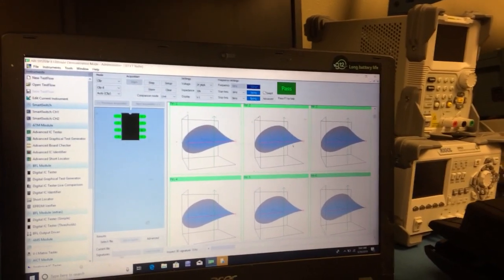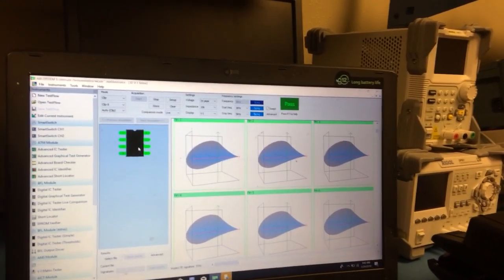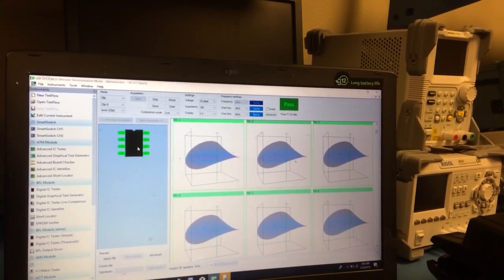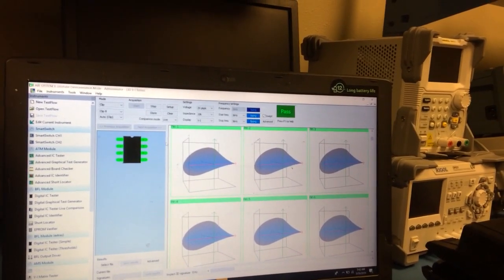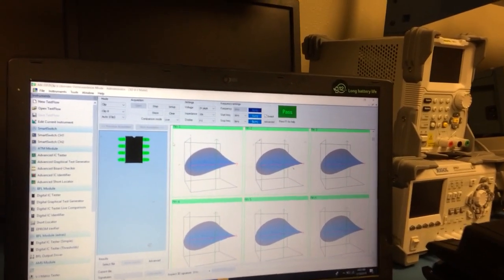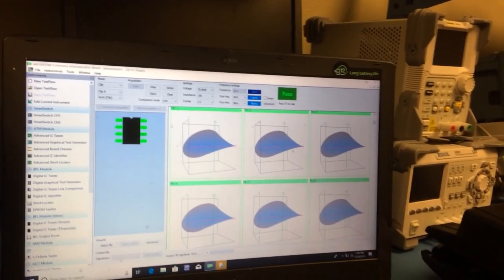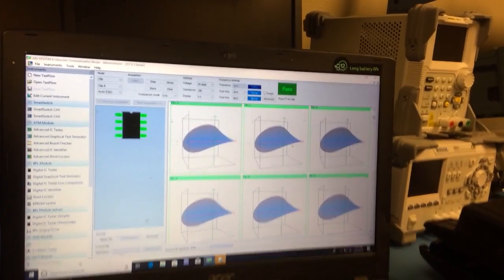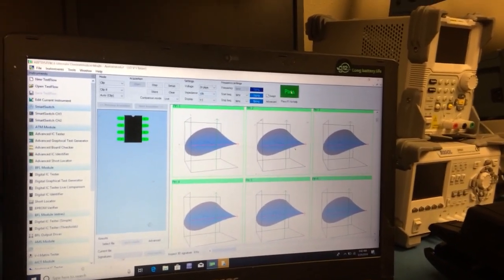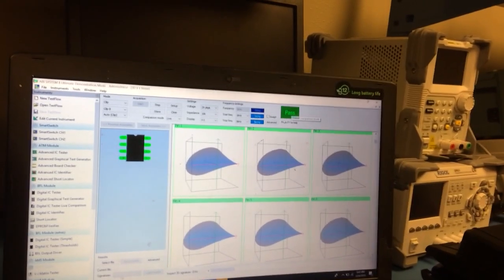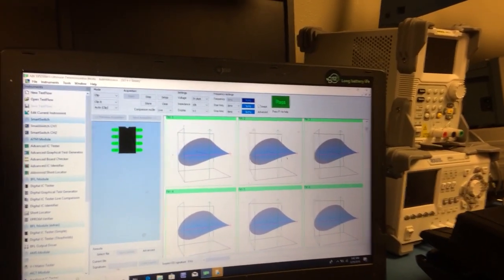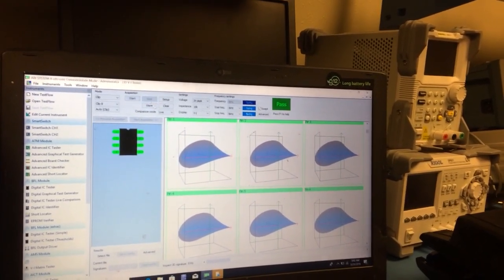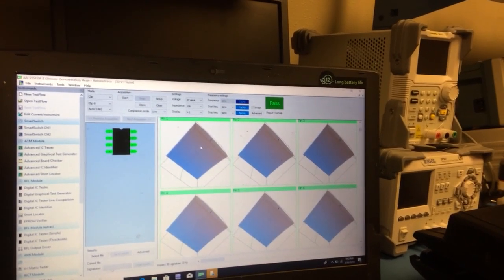We'll scan through the pins. If you have it hooked up, you can plug directly into a circuit board and do a comparison or a point for point comparison between a good board and a bad board. And you can set the tolerances for a pass-fail. We can actually stop this and freeze it.